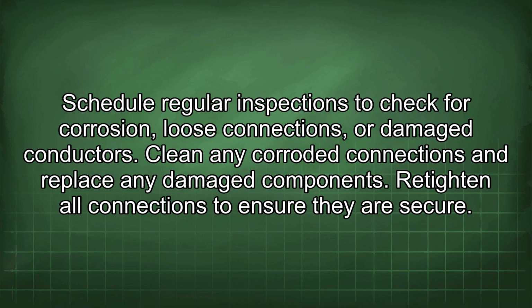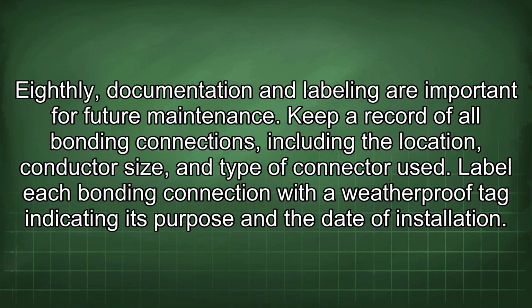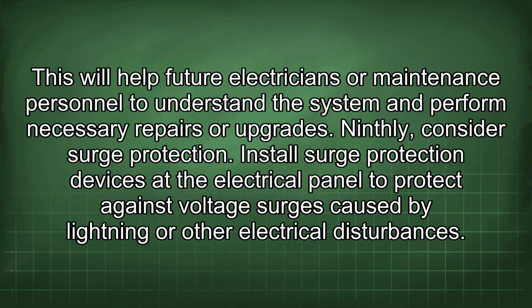Retighten all connections to ensure they are secure. Eighthly, documentation and labeling are important for future maintenance. Keep a record of all bonding connections, including the location, conductor size, and type of connector used. Label each bonding connection with a weatherproof tag indicating its purpose and the date of installation. This will help future electricians or maintenance personnel to understand the system and perform necessary repairs or upgrades.